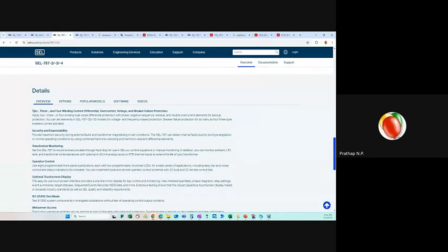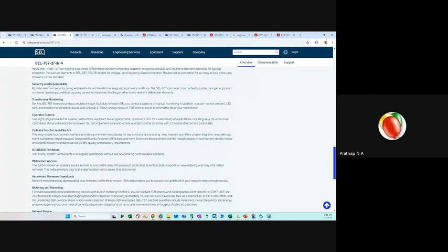Just the overview. You can have 2, 3, 4 winding current differential. It's very secure and dependable. There is transformer monitoring, like I said. You also have the legacy 4 to 20 milliamp. And I don't know if you have paid attention in Giridharan sir's session day 1. He said about the 4 to 20 milliamp. That has been there since the 60s and 70s. But that is still there, just in case, if you want to retrofit a new digital relay in an older substation, you can still use this.